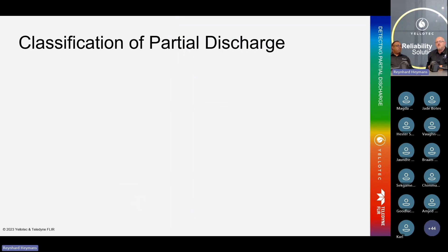So judging by sound, are you able to differentiate between the three? No, I just hear the buzzing sound. But the SI124 can do this. The SI124 uses machine learning and AI to tell you what type of discharge it is, be it corona, arcing, or tracking. And again, Ray, you made mention of the software. All you've got to do is plug the unit into your PC, extract the images, and the software does the rest for you.